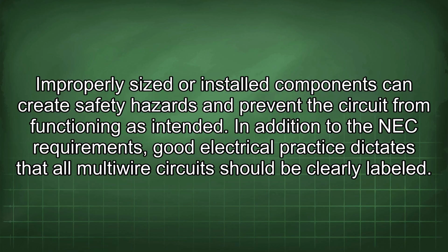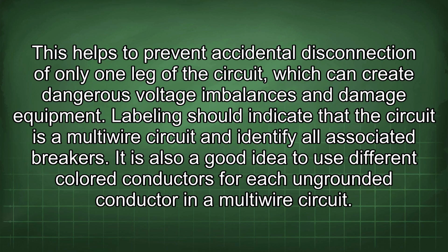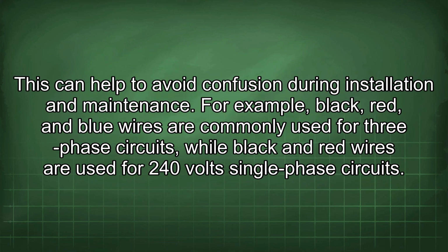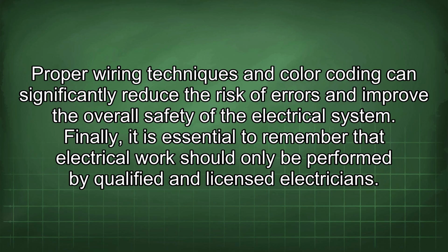In addition to the NEC requirements, good electrical practice dictates that all multi-wire circuits should be clearly labeled. This helps to prevent accidental disconnection of only one leg of the circuit, which can create dangerous voltage imbalances and damage equipment. Labeling should indicate that the circuit is a multi-wire circuit and identify all associated breakers. It is also a good idea to use different colored conductors for each ungrounded conductor in a multi-wire circuit. This can help to avoid confusion during installation and maintenance. For example, black, red, and blue wires are commonly used for three-phase circuits, while black and red wires are used for 240-volt single-phase circuits. Proper wiring techniques and color coding can significantly reduce the risk of errors and improve the overall safety of the electrical system.